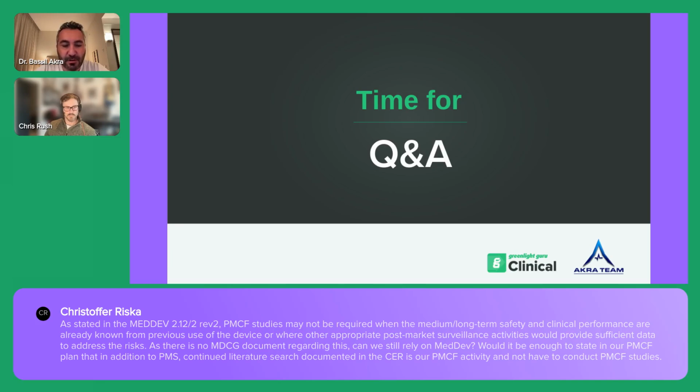So I give you an example just to make it much more visual for you. If you have a device which has an expected lifetime of 5 years, and you look to the key safety and performance criteria, which are extracted from state-of-the-art, and you have 5 years clinical data addressing those key safety and performance criteria, there is no open question to do a specific PMCF, so you can rely solely on the general PMCF and you stop doing proactive specific PMCF.